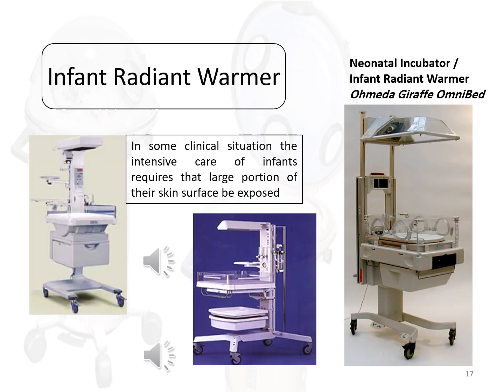In the infant radiant warmer, the artificial heating is provided by a heating mechanism mounted overhead. The heating mechanism consists of a radiant element, an electric heating element, and a heat reflector. Above this, the heater helps focus the radiant energy onto the mattress at the infant's location. The current through the heating element must be carefully controlled so that sufficient heat to maintain the infant's temperature is provided but overheating is avoided.